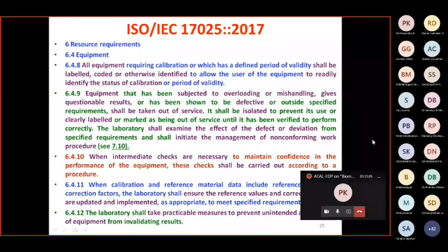Similarly, any equipment which is damaged, mishandled, or overloaded at any particular point of time, please isolate it, put a proper label on it, and ensure it is not put into use in future unless it is set right, checked for its validity and brought back into the system. Similarly, when you run a calibration equipment, it may call for intermediate checks as per the procedure given by the equipment or instrument supplier. Please list it out in your SOP and ensure they are all done and records are kept properly. Similarly, the reference data, reference values, and reference standards, whatever you use, ensure they are all properly updated as per the latest requirement and are available.